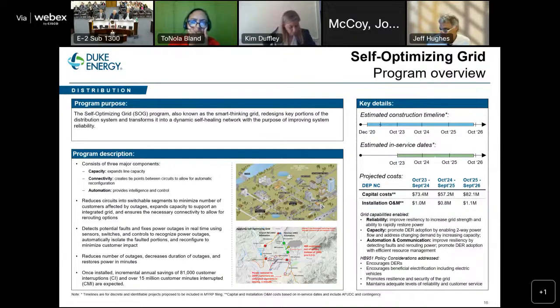You'll also see what looks like a cloud and a lightning bolt toward the upper left center. That indicates that between those two green boxes we actually have a fault condition on the circuit. In less than a minute, the system has determined where the fault is, opened those two green switches — green means open for us — and then closed all the other appropriate switches to restore as many customers as possible, all without human intervention. The operators in the control room are aware of what's happening and can take additional steps as necessary, but that's what the self-optimizing grid does.